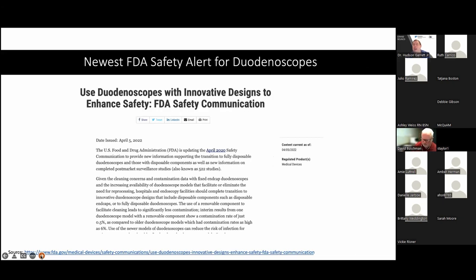So the next day, FDA issued another safety alert and talked about the risk associated with duodenoscopes. They continue to see outbreaks. They went further in this one and said not only should you look at reprocessing, but you need to move to sterilization. And if you can't move to sterilization, you should essentially reassess what you're using.